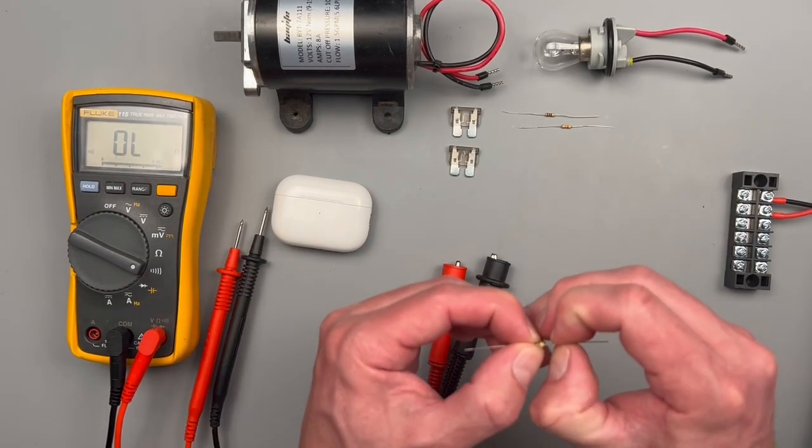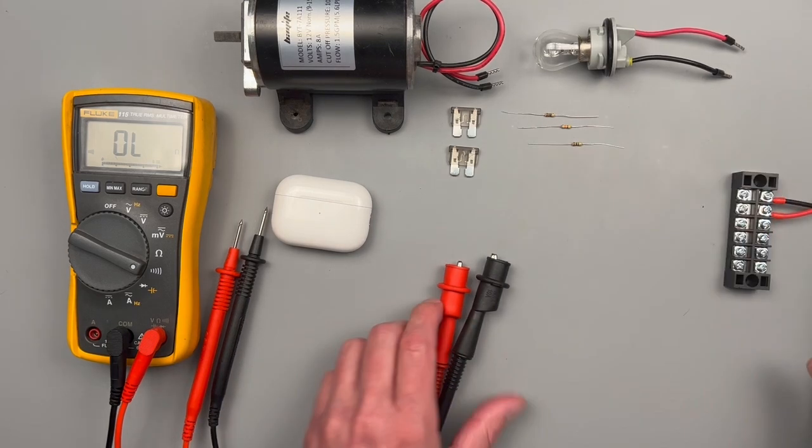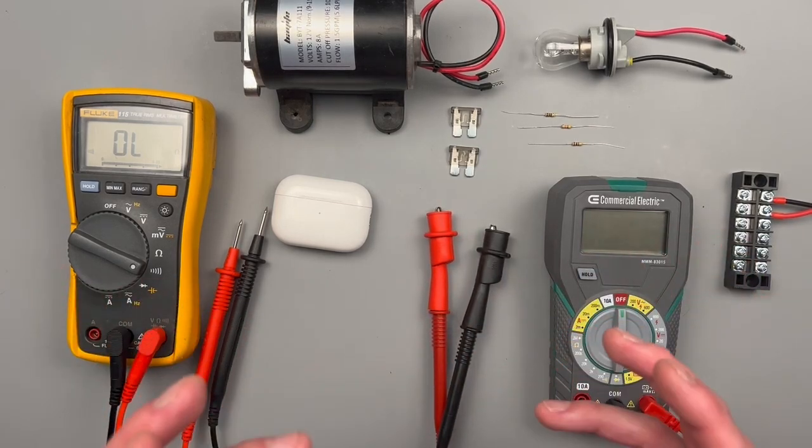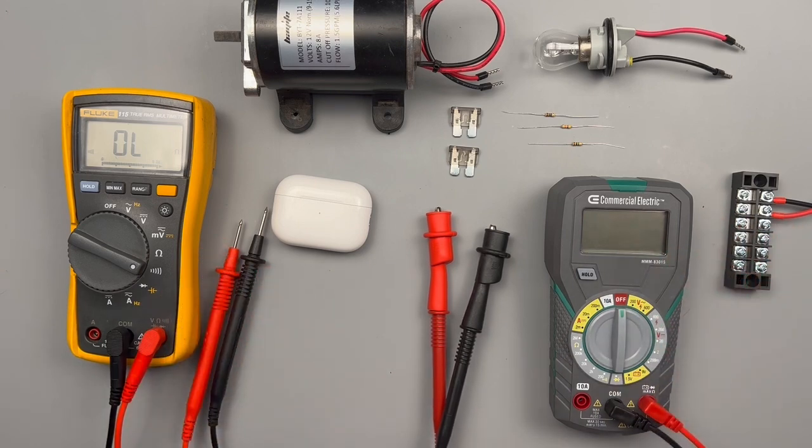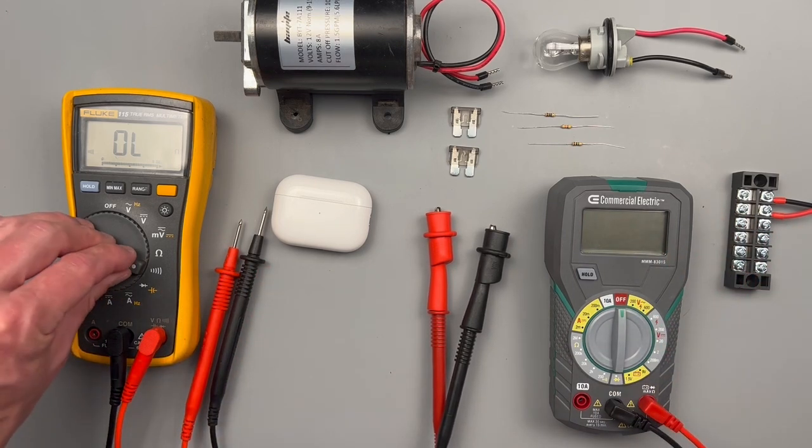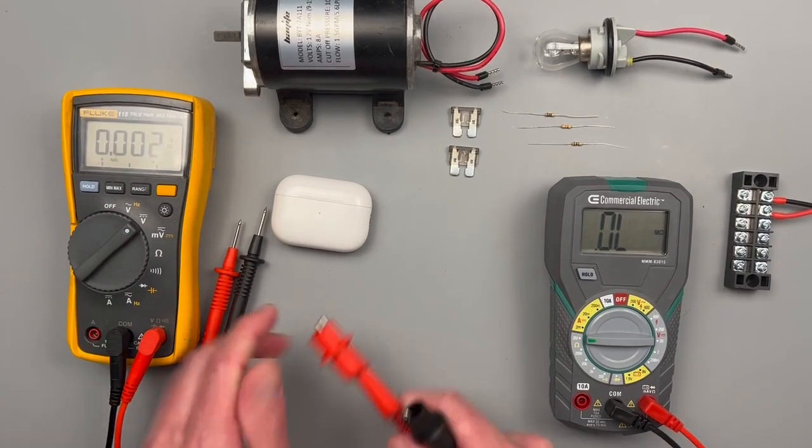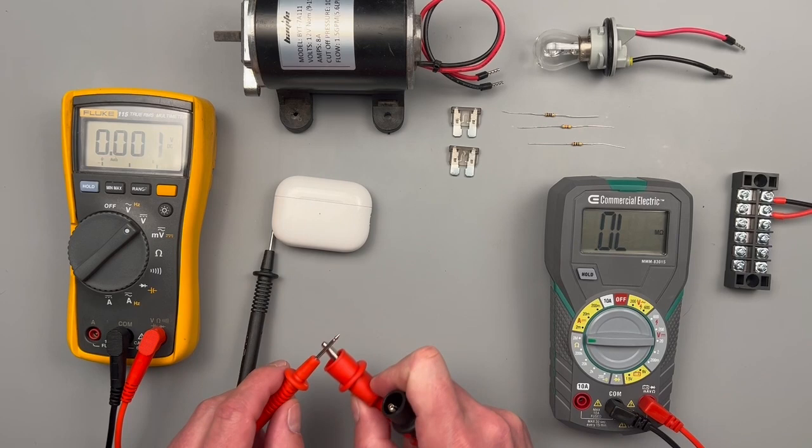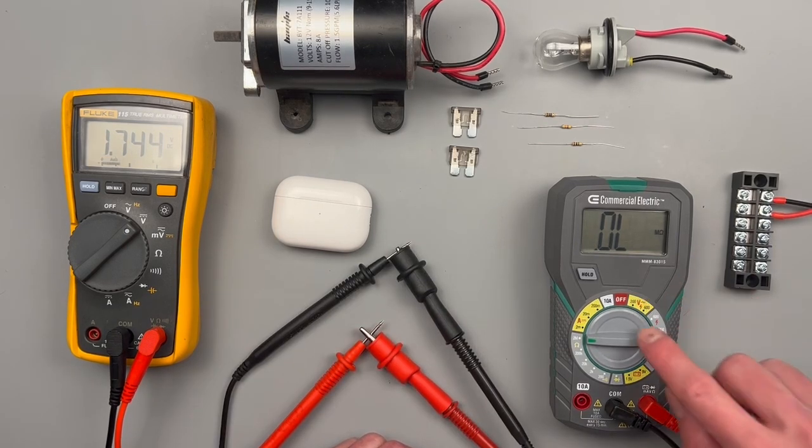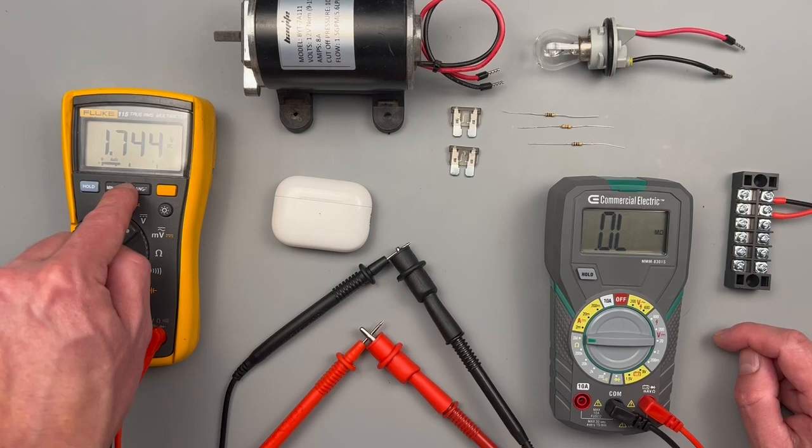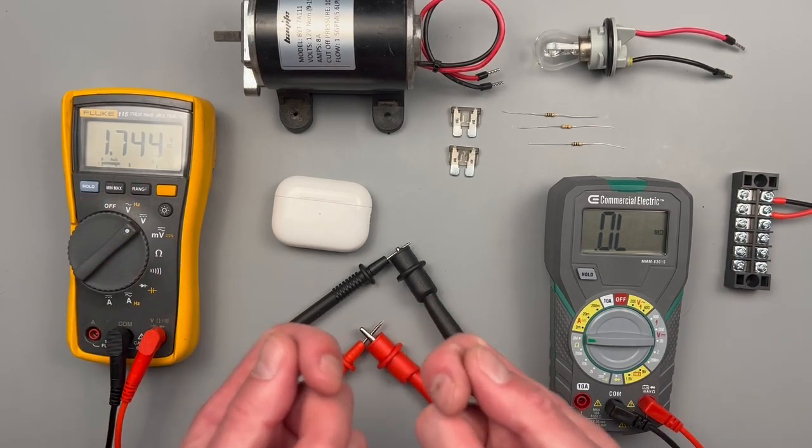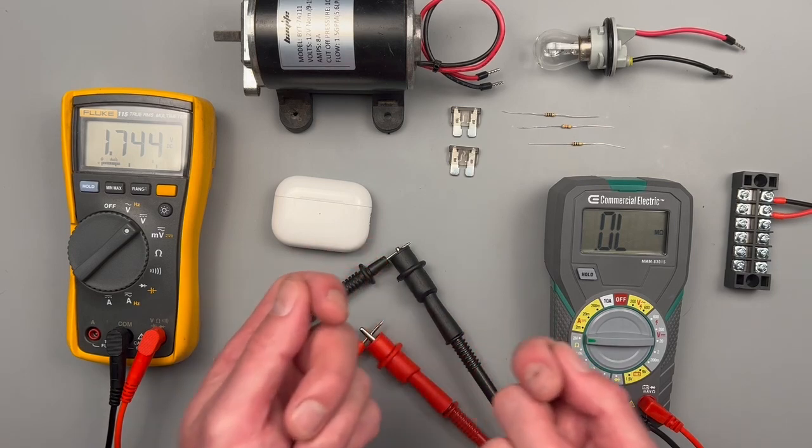The first thing that we want to keep in mind when measuring continuity and resistance is that it needs to be done on a dead circuit. All the power needs to be shut off and disconnected before we make resistive and continuity measurements, and I'll tell you why. When we measure resistance on our meter, we're actually outputting a small amount of voltage. You can see for this meter when it's trying to read a resistive value, it's outputting 1.7 volts DC. So you can't use voltage to measure resistance where there's voltage present.